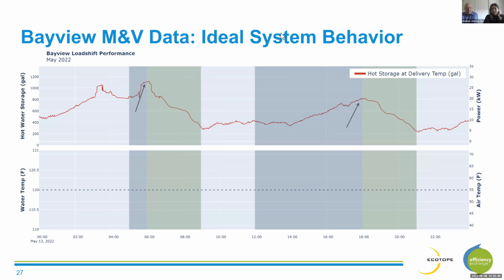There's two reasons for this. Reason number one is that at 5 a.m. when we're loading up the tank, not very many people are awake at that hour using hot water. And so the system isn't having to compete with much hot water use. Whereas in the afternoon, especially at Bayview, there are tenants in the building using hot water. And so in the afternoon, the system is not only having to keep up with the hot water usage, but also generate additional hot water to charge up our tanks.